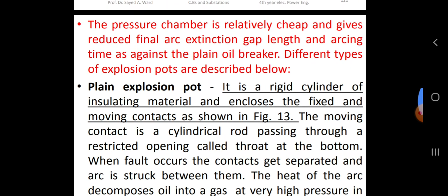Plain explosion pot. It is a rigid cylinder of insulating material which encloses the fixed and moving contacts as shown in the figure. The moving contact is a cylindrical rod passing through a restricted opening called the throat at the bottom. When a fault occurs, the contacts get separated and an arc is struck between them. The heat of the arc decomposes the oil into gas, creating very high pressure in the pot. This high pressure forces the oil and gas through and around the arc and extinguishes it.